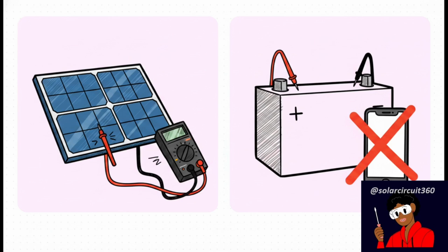Step 2 is battery voltage. You have to measure this directly at the battery terminals with a multimeter, not through an app. Relying on a smartphone app to measure your battery voltage is kind of like trusting a weather app to tell you if it's raining instead of just looking out the window. A direct measurement is the only way to confirm the actual state of charge and verify wiring integrity. Your app is never going to tell you if you have a dangerous voltage drop across a loose cable.